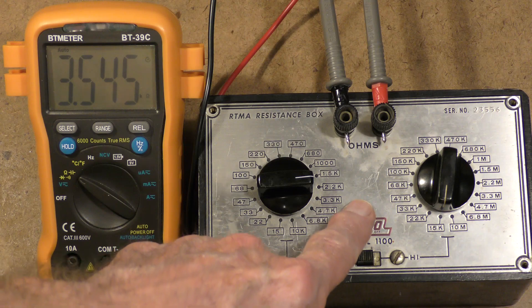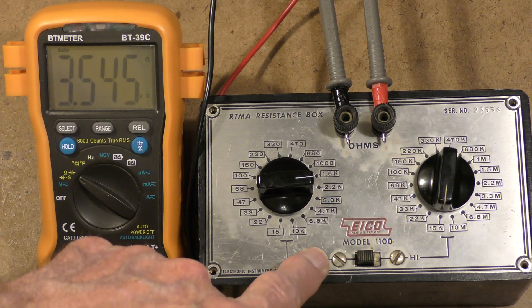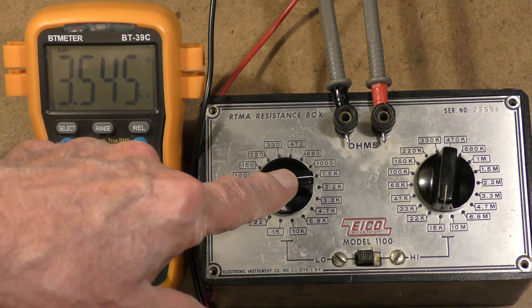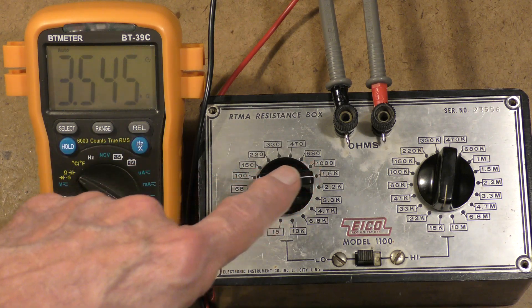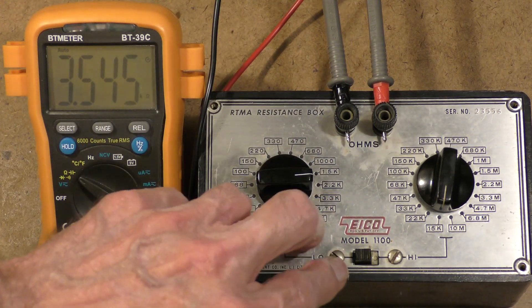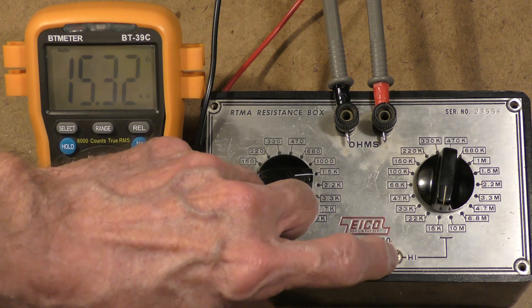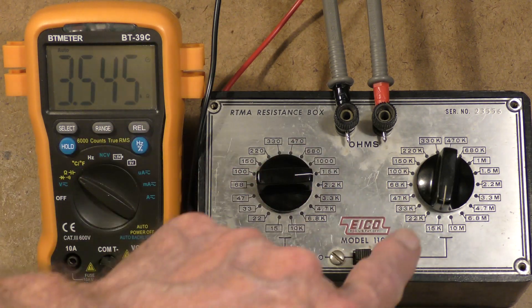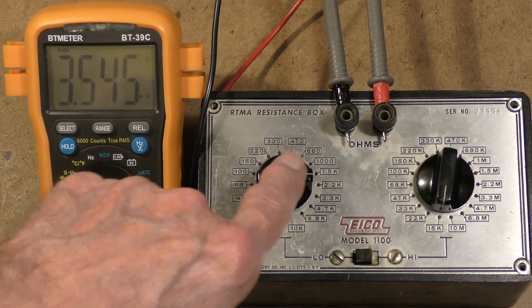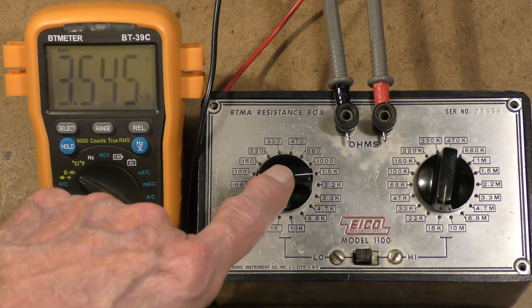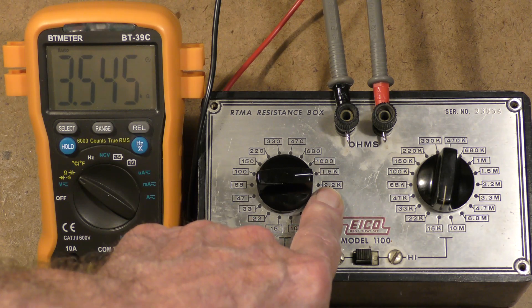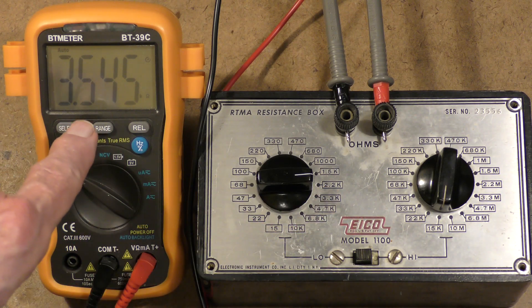This is a resistance substitution box and one of the problems with these boxes is the resistors in them often are carbon composition which tend to drift up with age. You can see that here. This is set to 2.2K. This switch switches from high resistance, which is this knob, to low resistance. Now I've already cleaned the contacts inside on the switch as well as on these rotary switches and I have verified that the problem is that the actual resistor that should be 2.2K is actually reading 3.5K.